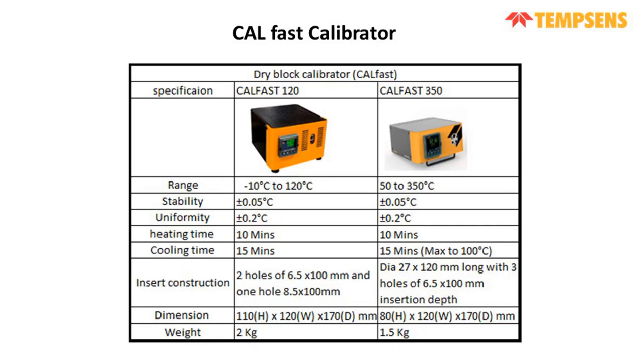Then we have CalFast calibrators. These are very lightweight models. Like this CalFast 120 is just 2 kgs, and CalFast 350 is just 1.5 kg. CalFast 120 has a range of minus 10 to 120 degrees centigrade, a stability of plus minus 0.05 degrees centigrade, and a uniformity of plus minus 0.2 degrees centigrade. The heating time is 10 minutes, and cooling time is just 15 minutes. And then again we have insert constructions. The standard insert construction is 6.5, and the immersion depth for the RTDs or thermocouples is 100 in this case, and one hole is 8.5. Then we have a weight of just 2 kgs.